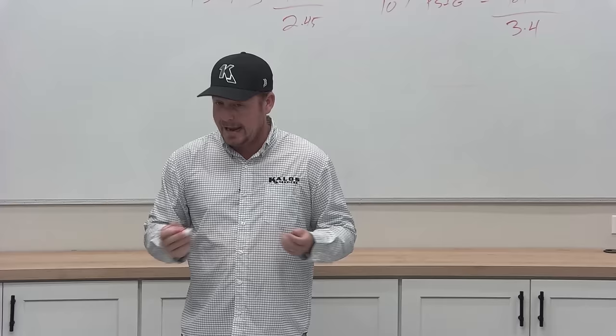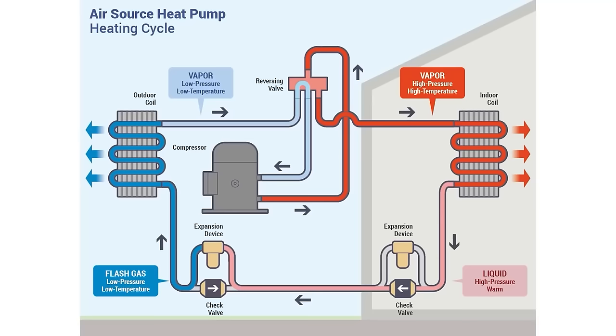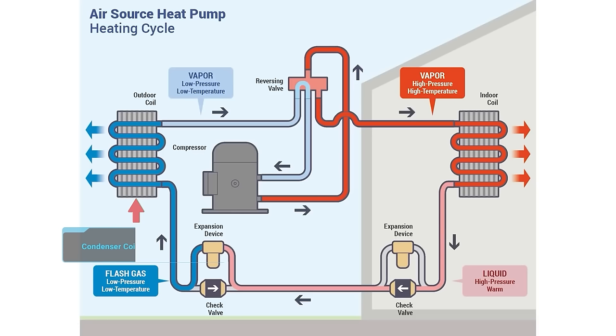In heat mode, if your outdoor coil — the artist formerly known as the condenser coil — is dirty, that causes low suction, which causes high compression ratio, which equals bad efficiency.